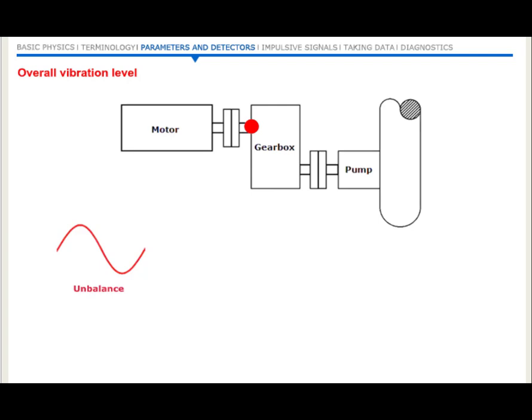This vibration results from the centrifugal force induced by the unbalance. The frequency of that vibration will therefore equate to the rotating speed of the motor. That is, if the motor is rotating at 1500 RPM, then the vibration frequency will be 1500 CPM or 25 Hz. There will probably be some vibration resulting from misalignment in the coupling. Again, this may not represent a problem, but it will still be present. Vibration resulting from misalignment will logically occur at a frequency relating to the RPM of the offending shaft. Depending upon the nature and severity of the condition, it may occur at various multiples or harmonics of the shaft speed. For the purpose of this exercise, let us imagine that the vibration occurs at 2 times shaft speed frequency.